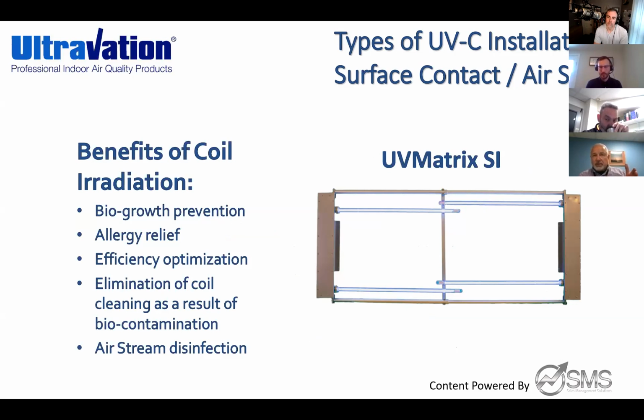So it is mounted before the coil, not after the coil, but it depends on the application and the space. I've seen them mounted after the coil too, because our goal here is just to get the light on the coil to inhibit growth. Depending on how much space, because I've never been inside your equipment. I took dimensions from the coil on the opposite side, because I don't have a lot of dimensions between the filter rack and the coil itself. So I do have a specific amount of room, and I think I sent you that information as well. Yeah, awesome.